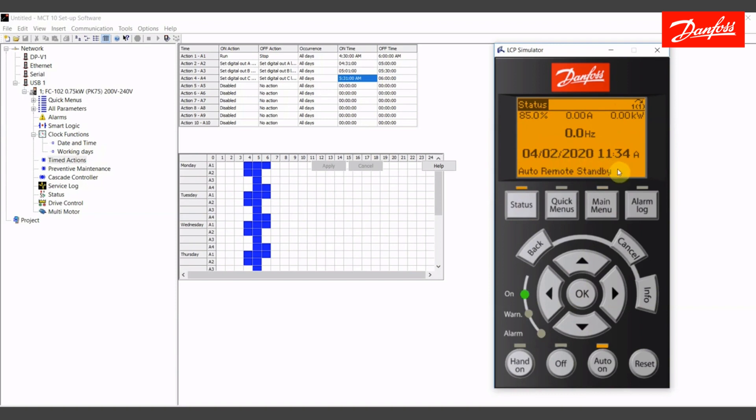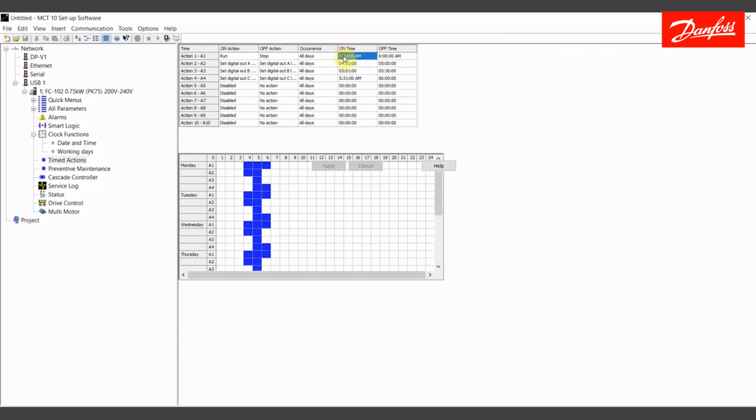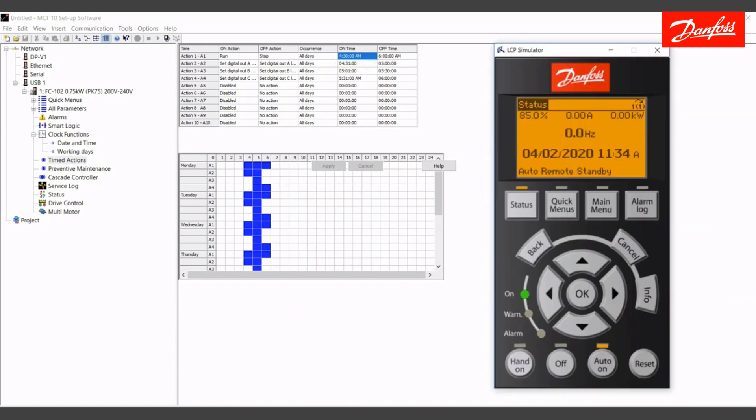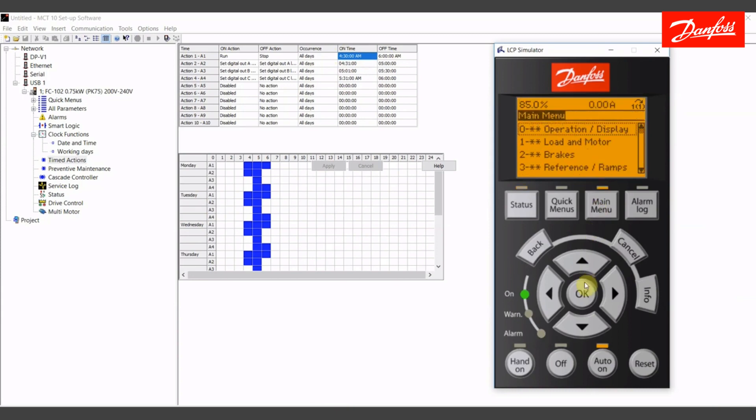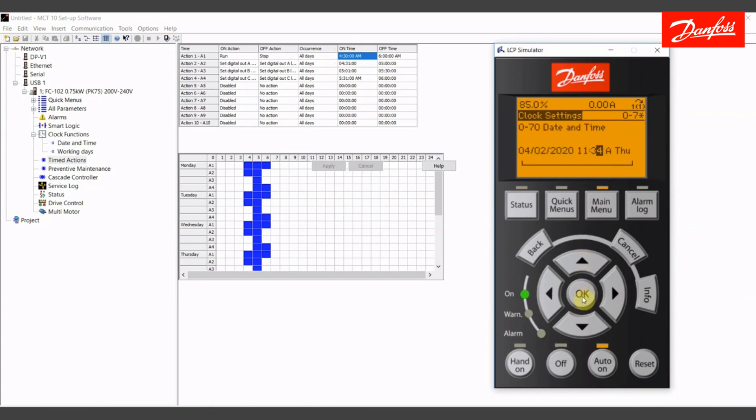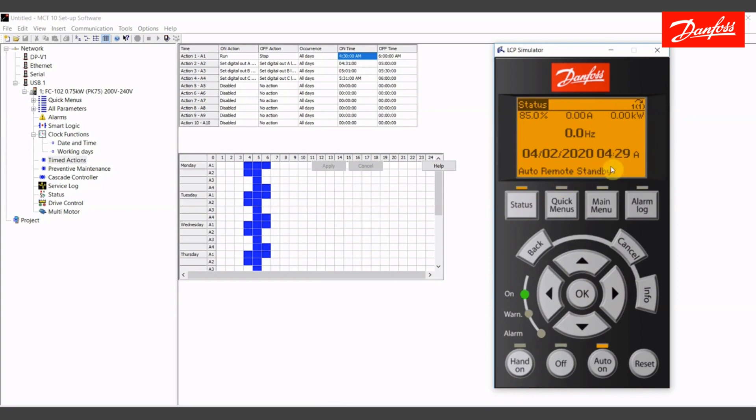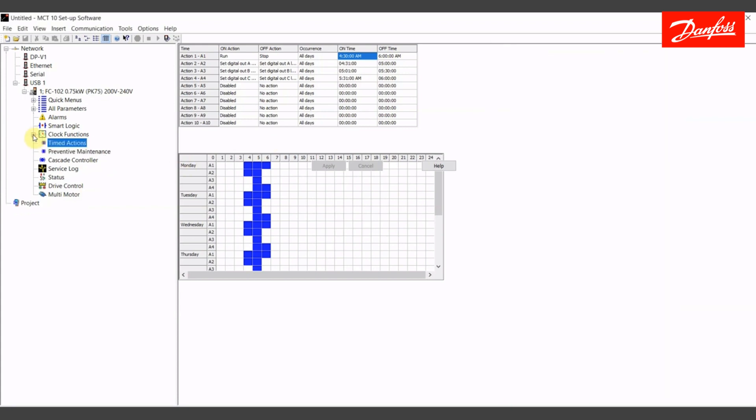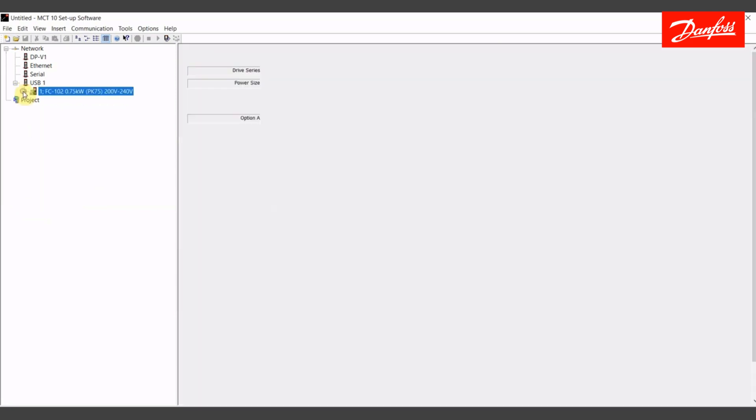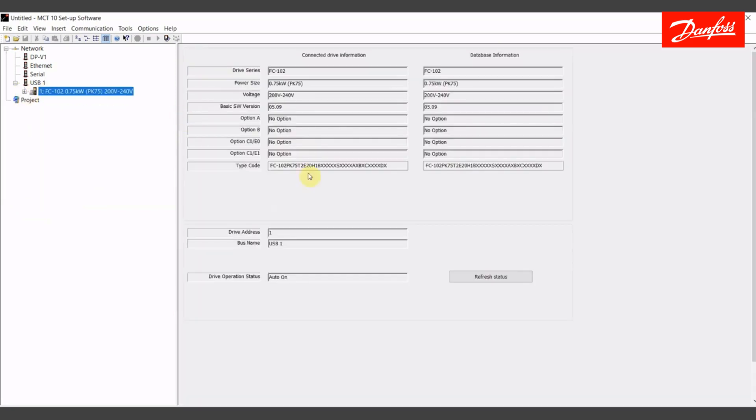This drive is currently in a standby state. So what I'm going to do is I'm going to force this drive to show a time of 4:29 a.m. Therefore, we can wait approximately one minute and we'll see something happen, hopefully. I'm going to go back to the time clock and set it for 4:29. One minute later at 4:30, we should notice that the drive goes into a run state. It currently has an 85% speed reference, so I'd expect for us to see that.